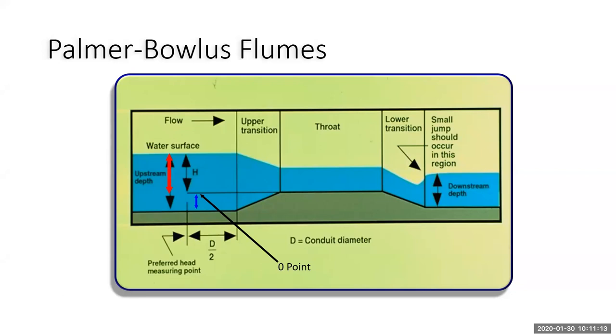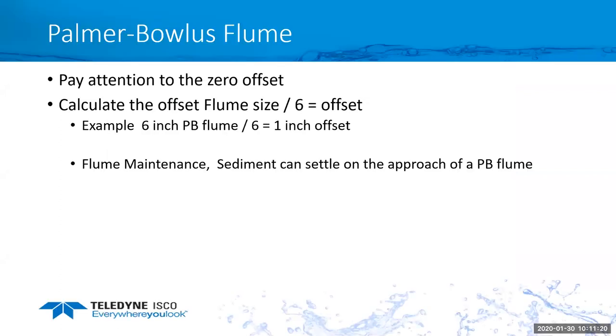So when doing this, you would measure the overall depth where the red arrow is and then subtract the upper transition. So you want to pay attention to the offset. The way you can figure out that offset, the formula is the diameter of the Palmer Bowlus flume divided by 6. So in this example, we have a 6-inch Palmer Bowlus flume divided by 6. The upper transition is 1 inch.